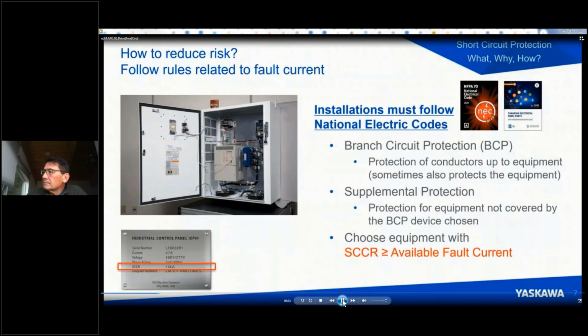Okay, and then the equipment that's chosen, such as an electrical panel, needs to be chosen such that its withstand capability, or the short circuit current rating, is greater than or equal to the available fault current for the power that's connected to it. So as you can see on this panel here, the panel has a short circuit current rating of 14,000 amps. So obviously if there was more available fault current where the power is connecting to this panel, it would not be sufficient, or the available fault current would somehow have to be reduced. Another important point here: when installing equipment, you absolutely must follow the equipment instructions, which we will get into some of these details.